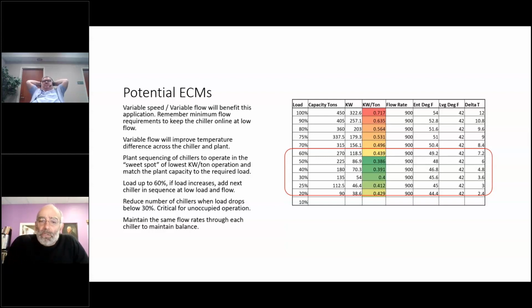So I had a couple questions. One is, and you or other people have heard me say this before, a lot of us engineers went to school, got really good at math and computer modeling and all that. And we end up using these curves, like these DOE-2 chiller curves, which assume at 100% load it's really hot outside, and at 50% load it's a lot cooler outside. Therefore, the condenser water temperature is different at different loadings. And so the curves we're getting from DOE-2 or Trace or whatever are crap. And we end up recommending staging sequences that don't make any sense, because what we really needed was a constant condenser water temperature coming in, so we could compare apples to apples when looking at the different loads of a chiller.